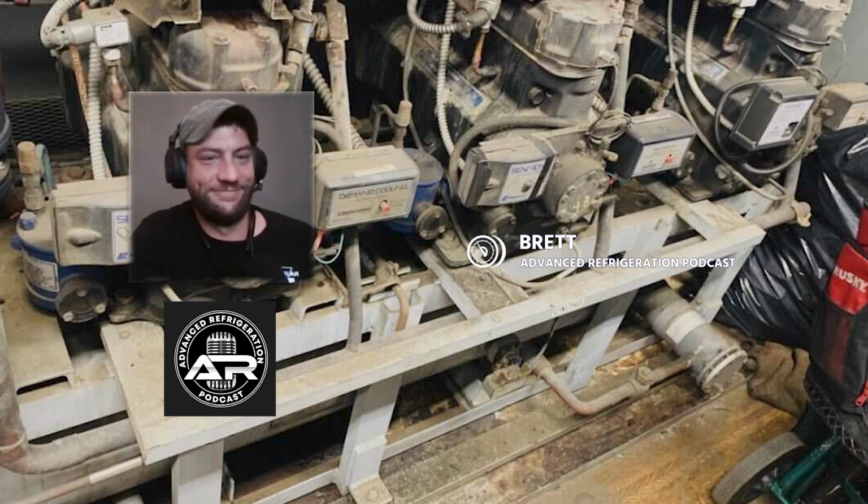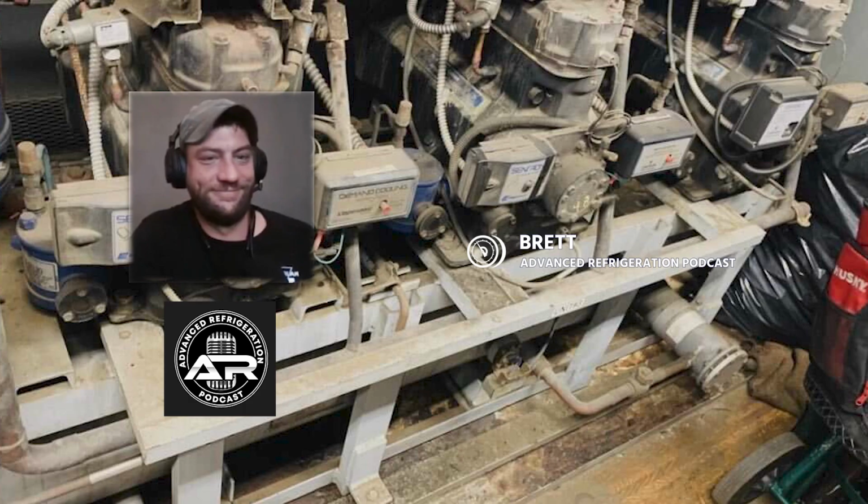If we refer to air conditioning, we usually maintain a 38 to 40 degree saturated suction, right? Yep. And then usually the discharge air is anywhere from 52 to 55, right? So that would give you approximately a 15 degree TD. That's what we refer to in refrigeration: it's basically the difference between your saturated suction and your discharge air. And that's what we're accomplishing here. If we're trying to maintain 35 degrees and it had a 10 degree TD, we'd set the evaporator for 25 degrees. Exactly the same premise that you do in HVAC, just with lower temperatures.